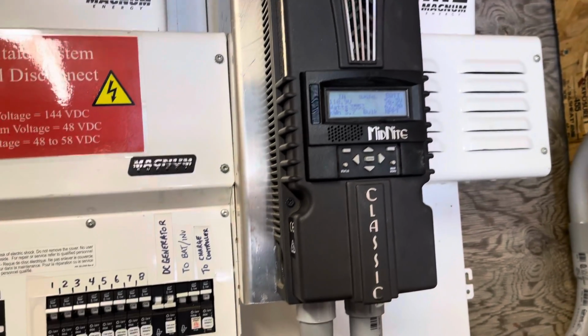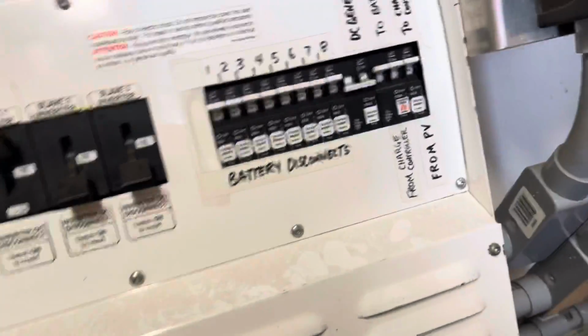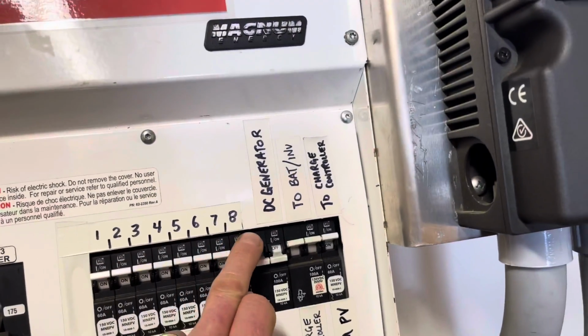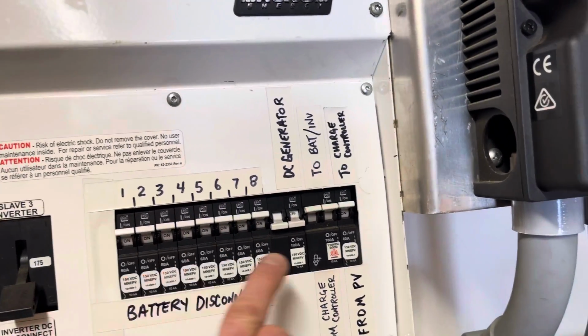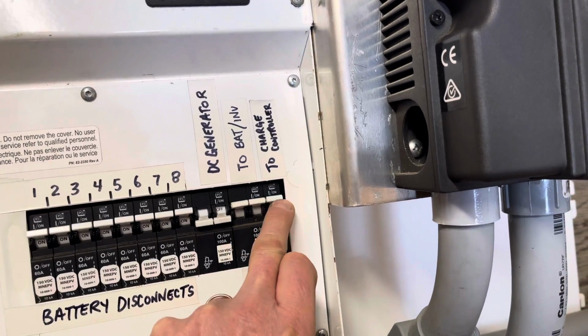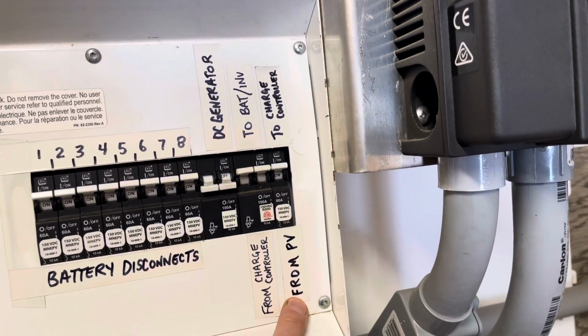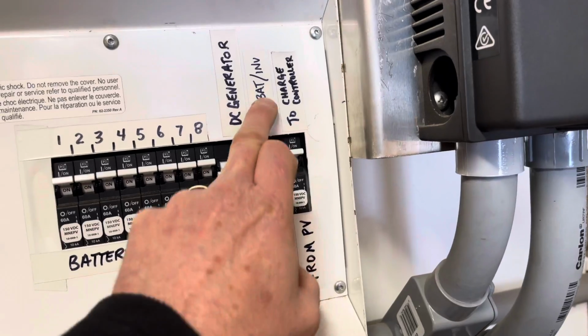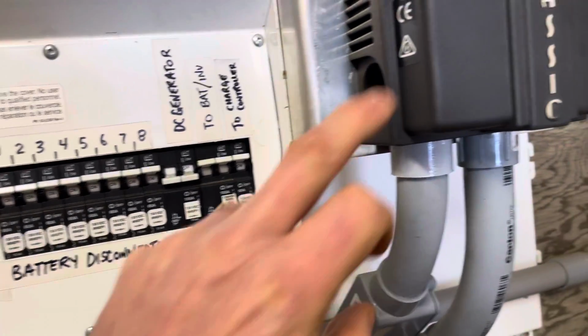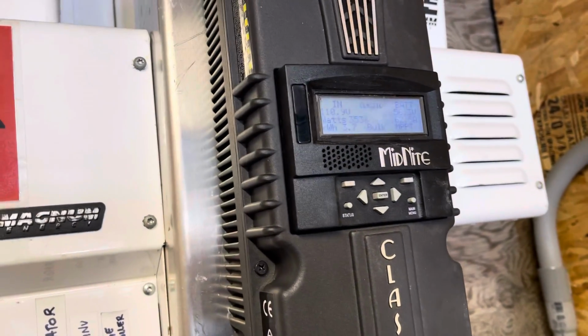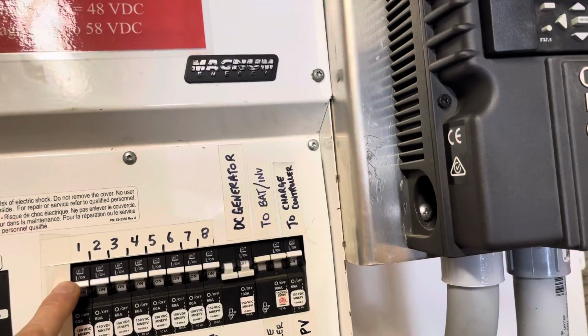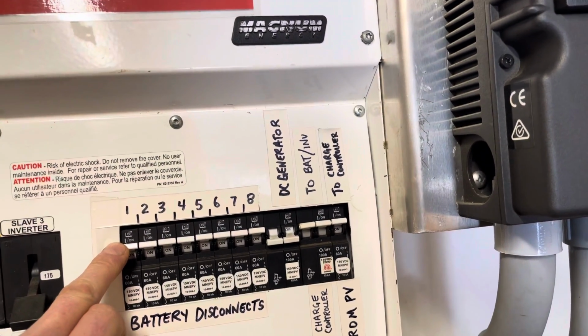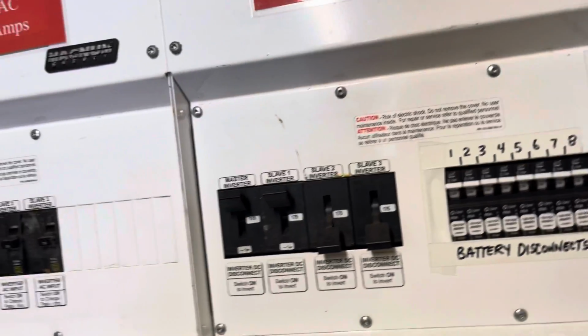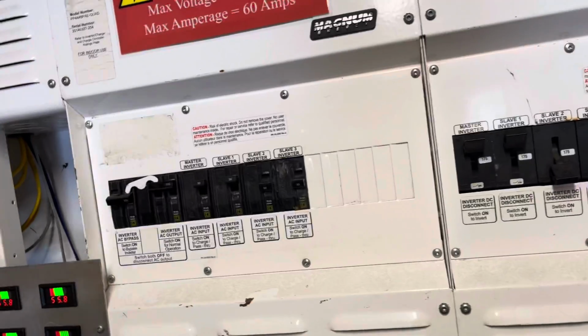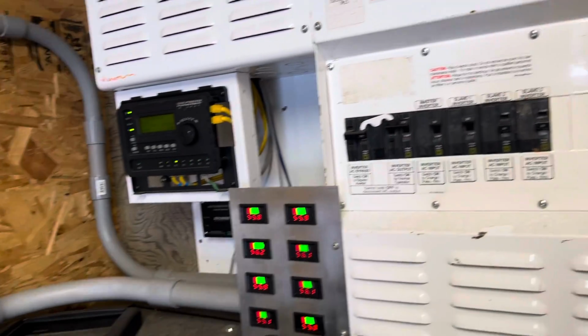At the time of the issue, I had all the battery disconnects off. So I turned on the power from the photovoltaic and the charge controller to the batteries, putting power onto the bus bar from the solar panels. Then I turned on just number one by itself, with everything else off, and shut the inverter completely off so there was no power going out to it.